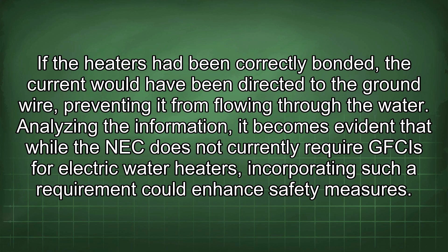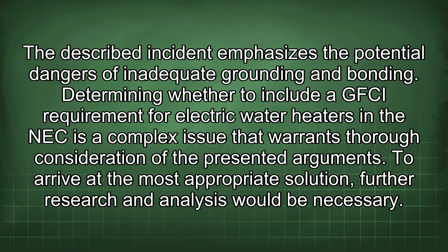Determining whether to include a GFCI requirement for electric water heaters in the NEC is a complex issue that warrants thorough consideration of the presented arguments. To arrive at the most appropriate solution, further research and analysis would be necessary. GFCIs function by monitoring the current flowing to and from an appliance or electrical circuit.